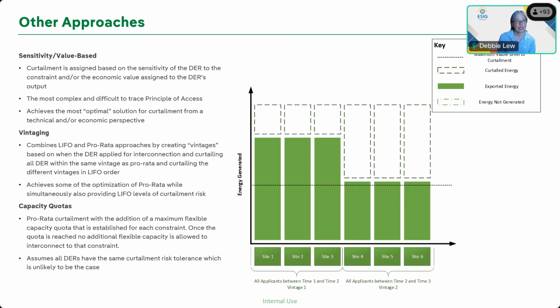Someone asks, should we provide a set point to each DER during curtailment to minimize fluctuations? Yeah, we are. So that threshold limit, or that maximum export limit, is that set point that they're supposed to meet. And if they do not meet it within a certain tolerance level, the local gateway starts taking action to trip them offline, because the security of the system is always prioritized. So if we're telling you to respond, regardless of if it's a network curtailment event or a non-network curtailment event, and that site is not following our direction, then that's a risk, right? We now have an uncontrolled site in a situation that could cause system violations. And so we take action right away to trip that site offline if they're not following our set point.